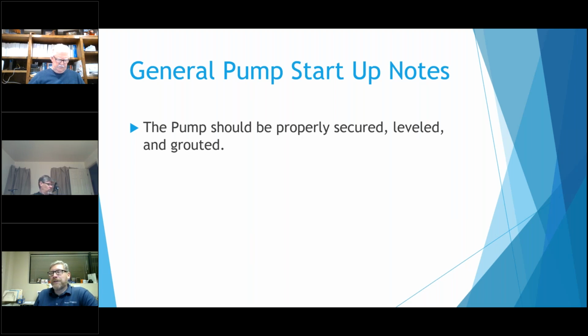Early in my career, I always thought that was just what I had to say, because that's what the IOM calls out. And I'd seen so many pump installations that didn't have vibration problems, until I ran into one that had a lot of vibration issues. Unfortunately, the pump was already picked on the end of its curve, and when you operate on the extremes of the curve, you pick up a lot more vibration. This was so bad that you could feel the whole floor vibrating from about 40 feet away, in another room, as you got closer. And I said, well, the pump's not grouted. Grouting would get rid of some of the vibration. I can't guarantee you get rid of all of it, but it'd get rid of some.